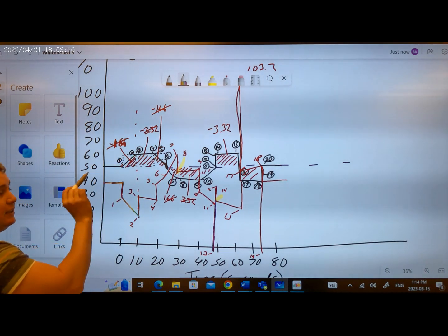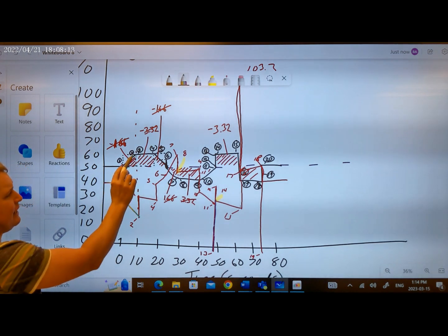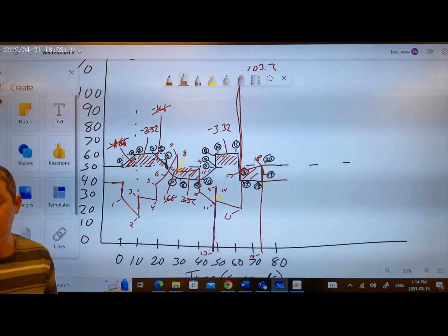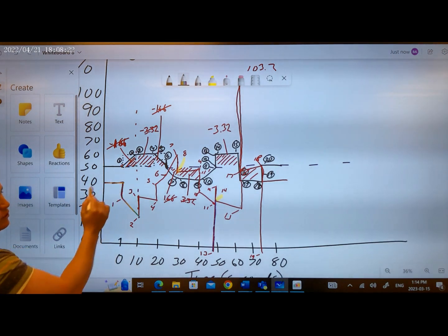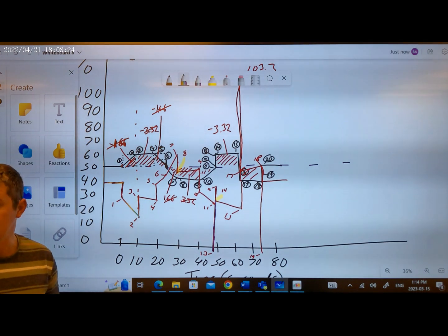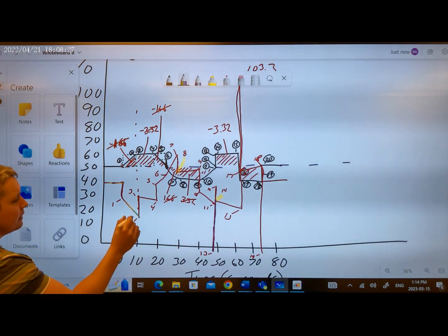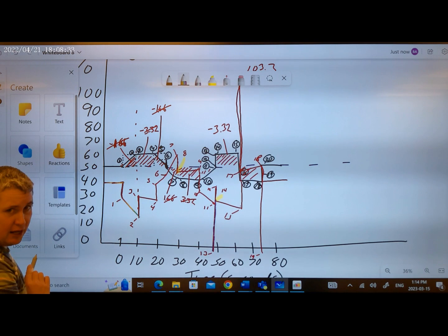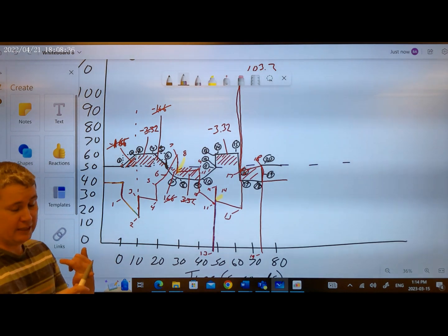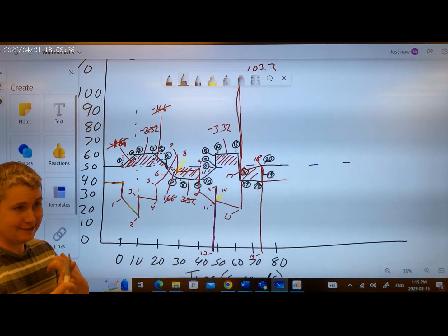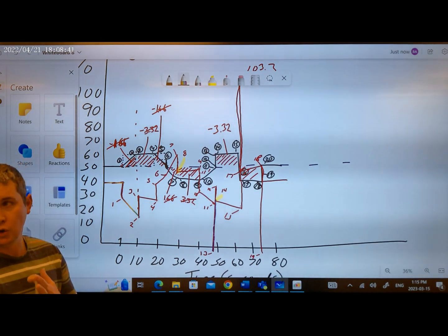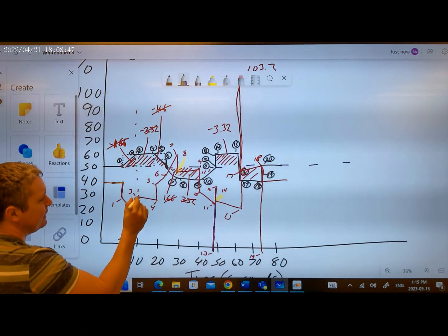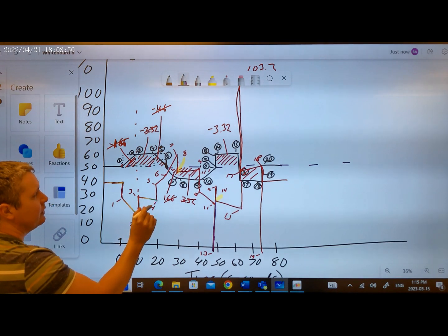Because it's ramping, you have derivative. Because the error at spot 2 is minus 10, you have proportional. Because we have all this area to account for of error, you have integral, right? Then it spiked back up due to the fact that the ramp rate stopped. The proportional is still there, the integral is still there, but the derivative no longer has that ramp rate.